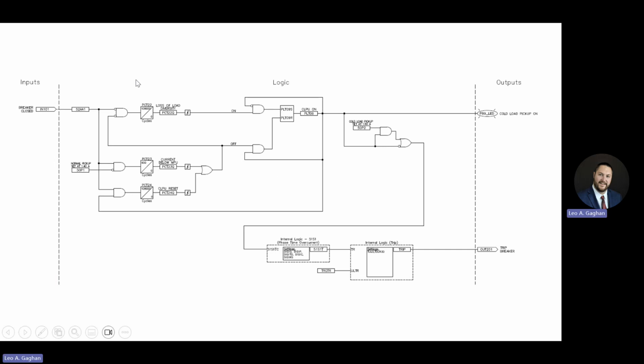Okay, so to run through this again, let's think of an initial condition. The breaker is closed. The breaker's been closed for a long period of time. Cold load pickup is off. So we'll call that our initial condition. Cold load pickup off, breaker's closed, right? Feeding load, and it's been closed for a long period of time.